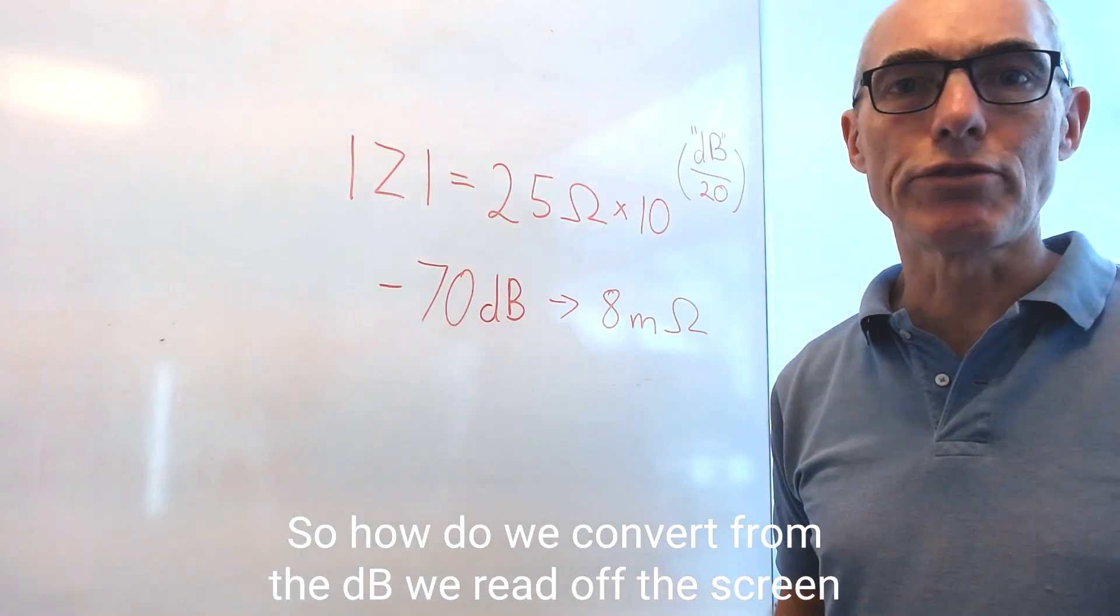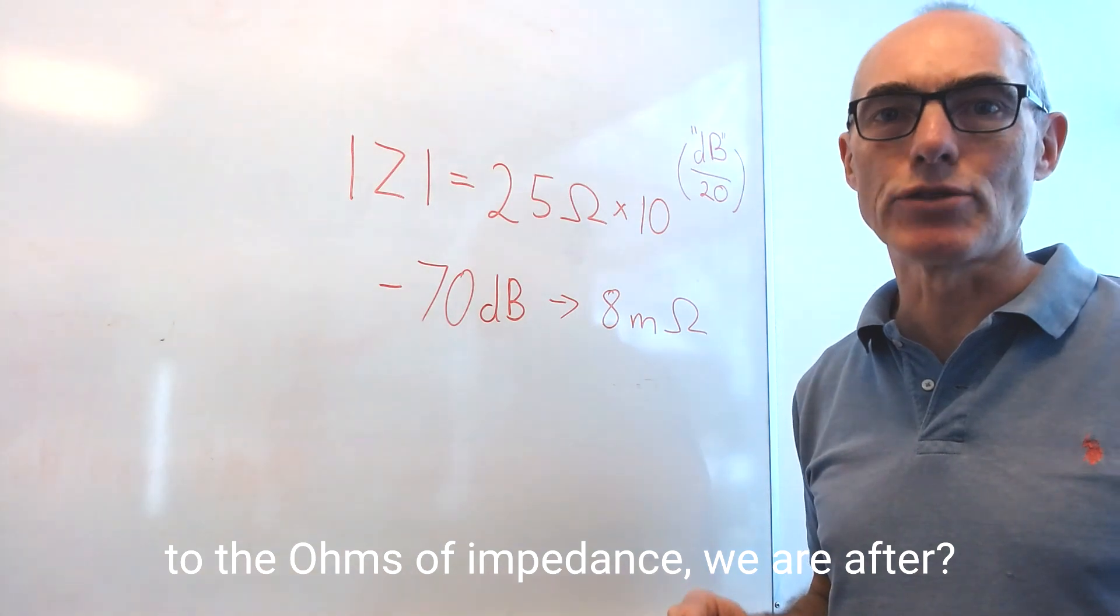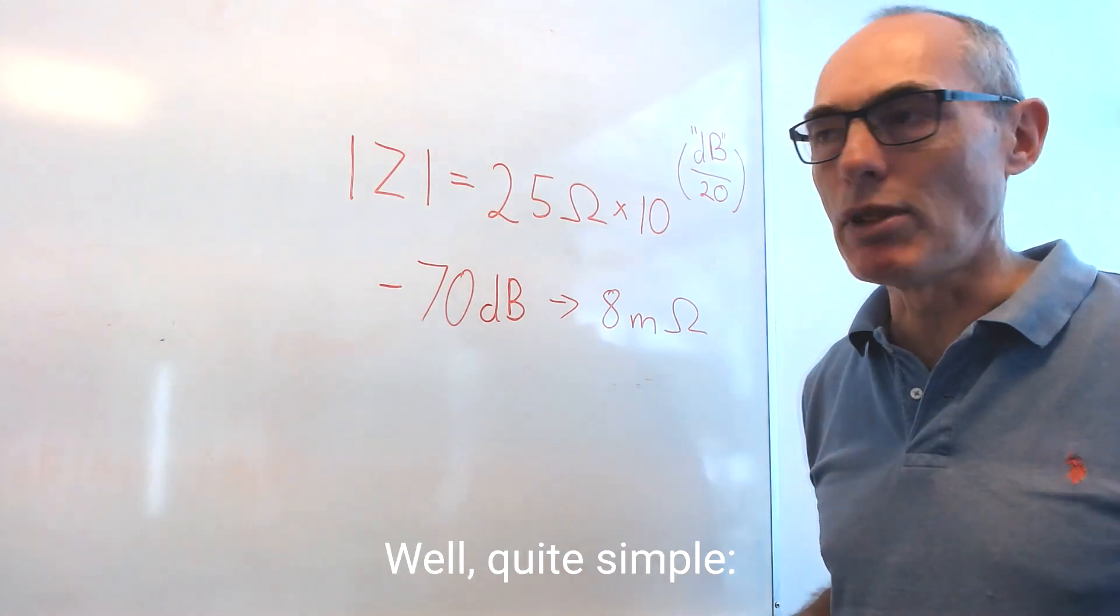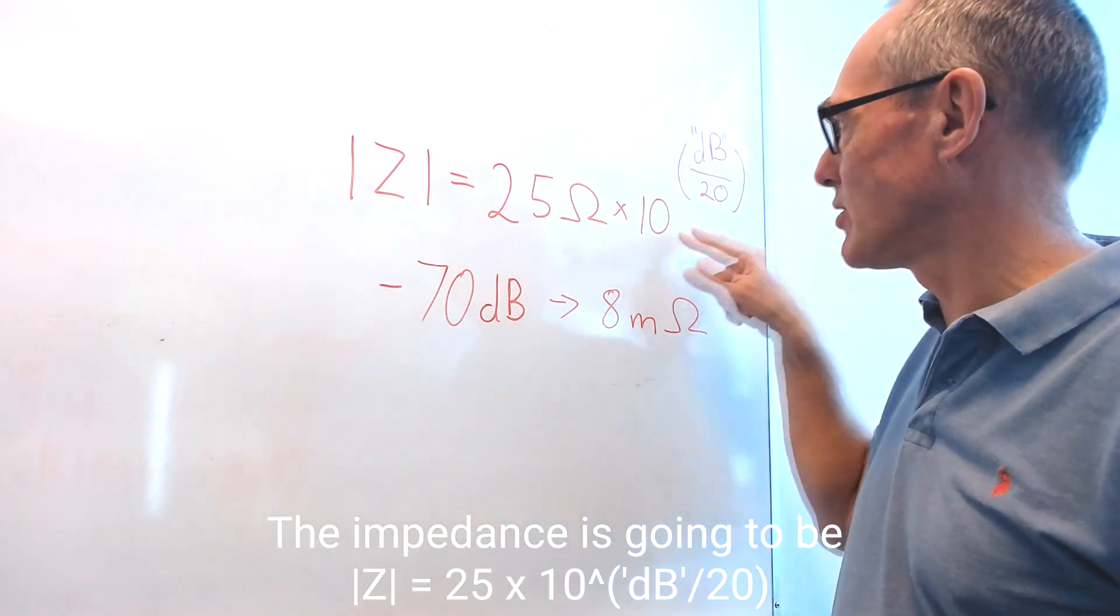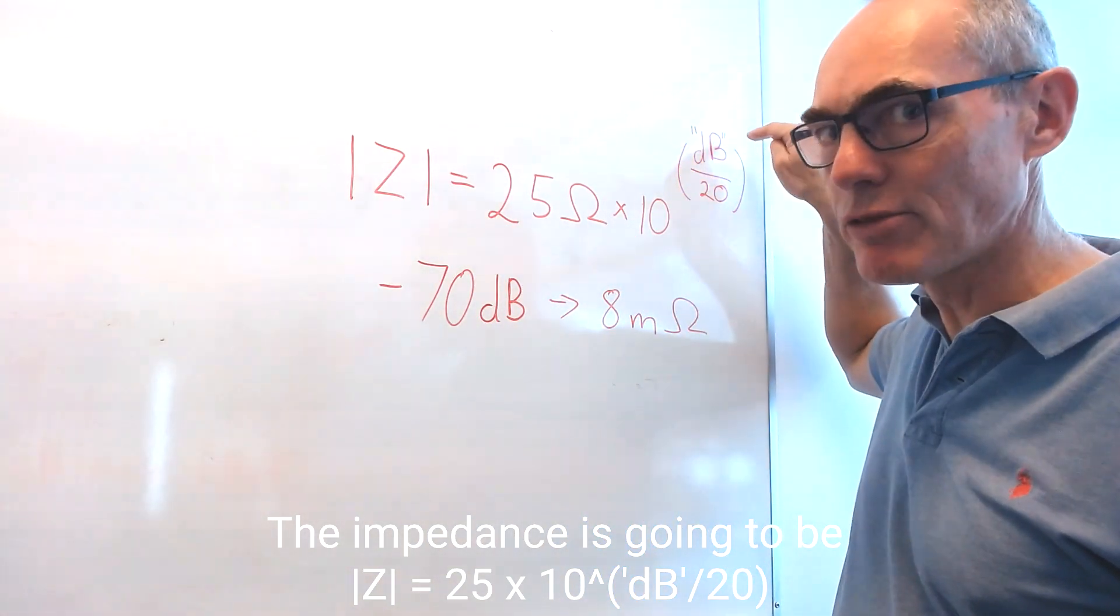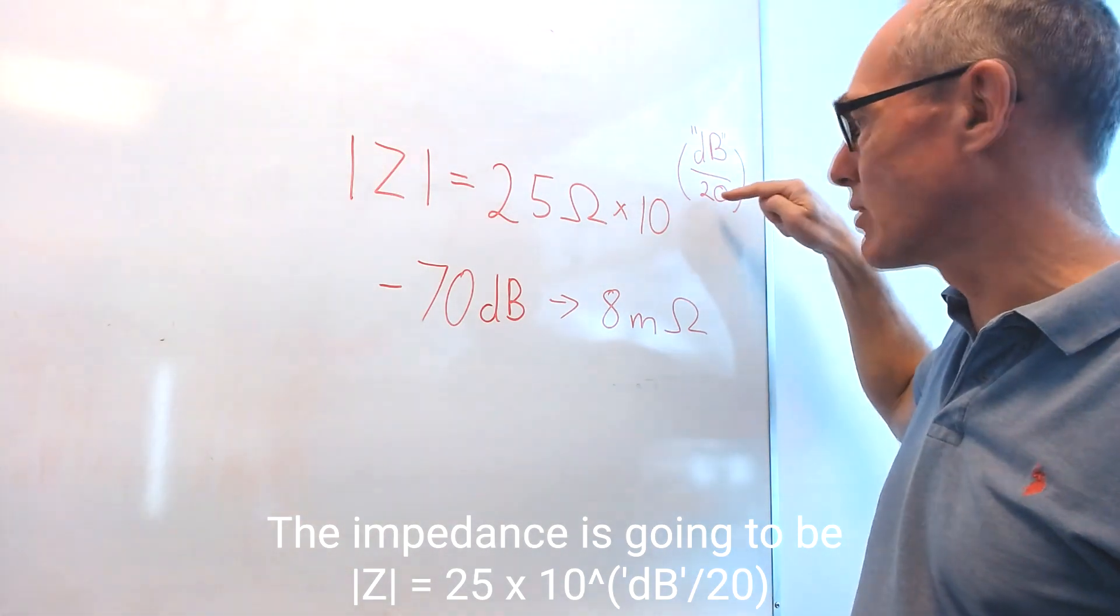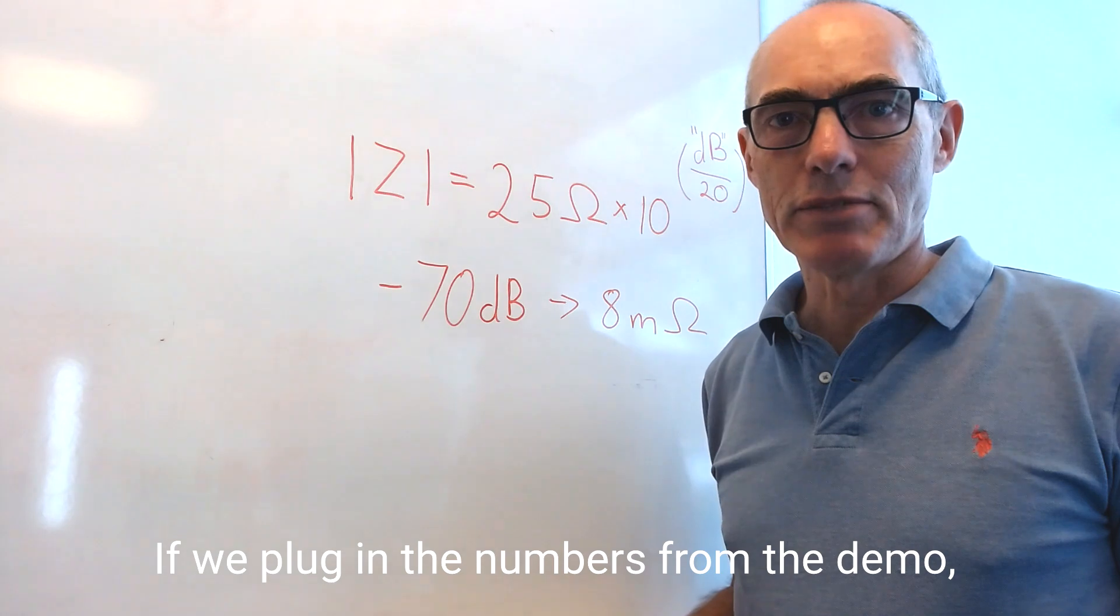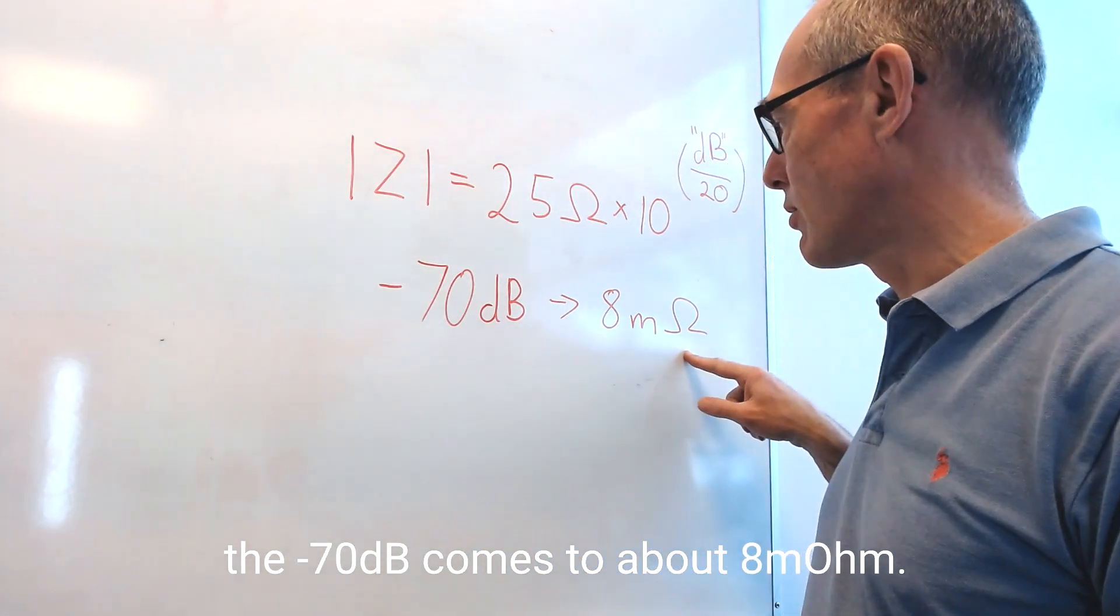So how do we convert from the dBs we read off the screen to the ohms of impedance that we're after? Well, quite simple. The impedance is going to be 25 ohms times 10 to the dBs that we read off the screen, divided by 20, so dB divided by 20. If we plug in the numbers from the demo, minus 70 dBs comes to about 8 milliohms.